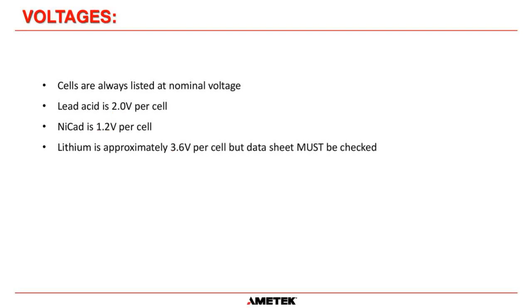Now, in the industrial UPS and switchgear world, the majority of batteries contain 60 cells of lead-acid batteries. So that is a nominal string voltage of 120 volts, because 60 times 2 volts is equal to 120 volts. For NiCads, they usually use 96 cells. That actually gives you a nominal voltage of 115.2. Some people will still refer to this as a 120 volt DC string. But you've also got to understand that the only thing that drives these voltage selections is the tolerance of the load circuits that they supply. And we'll go into that in a little bit.